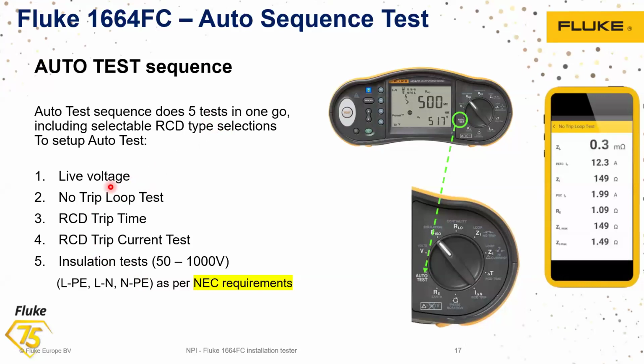That is the live voltage measurement. The moment you connect to a particular socket point, the electrical connection, it will directly detect the live voltage, and automatically do the loop impedance test with prospective short circuit current and fault current. Then RCD tests, then the insulation test. So RCD tripping time and tripping current, as well as the insulation test, it will complete with voltage ranging from 50 to 1000 volt.